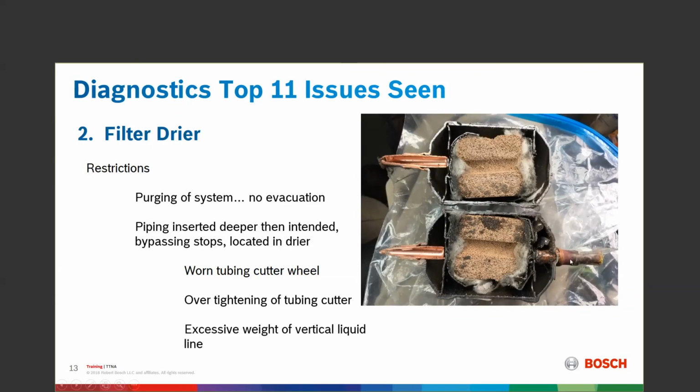This is a steel canister. This is the edge where, if you burn the paint off that dryer when you braze this in, or solder such as Stay Bright 8, this will rust over periods of time, and then the refrigerant will leak out through that dryer shell.